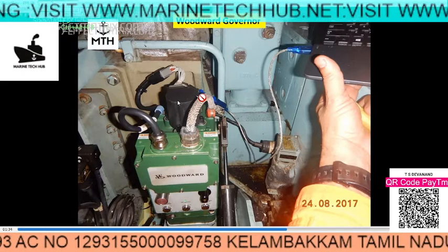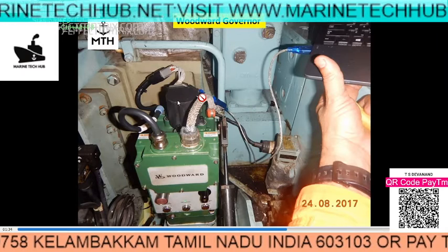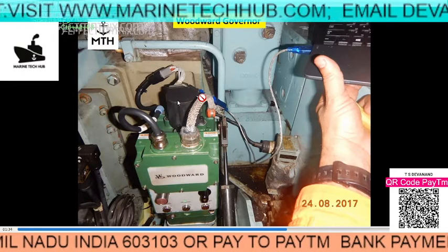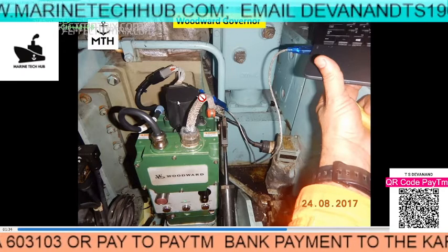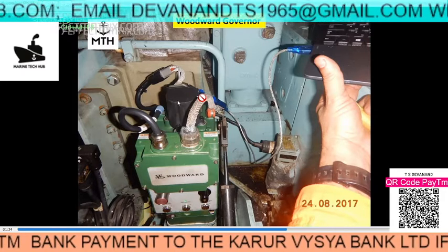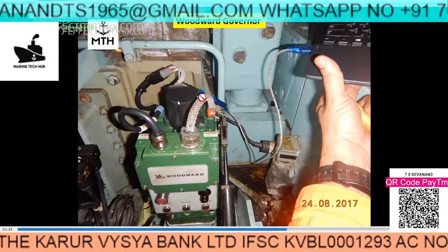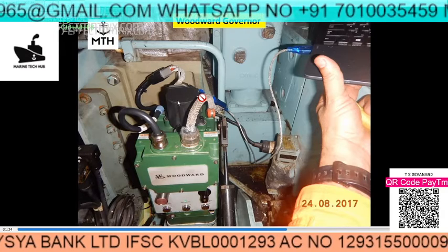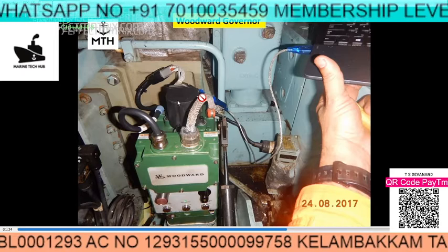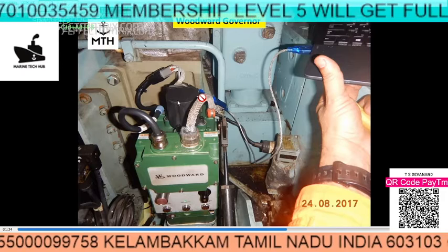This is very important for senior engineers and superintendents watching my videos. Please make note of the following things. One important spare is the governor motor, which is mounted on top of the Woodward's. This motor has a small bearing inside, and normally this bearing is of a different size, so order and keep at least one spare.